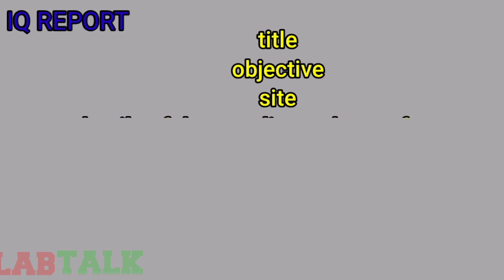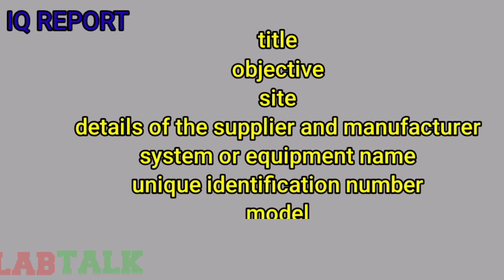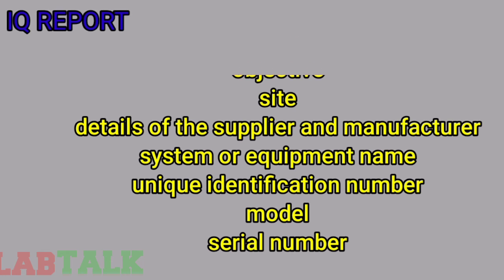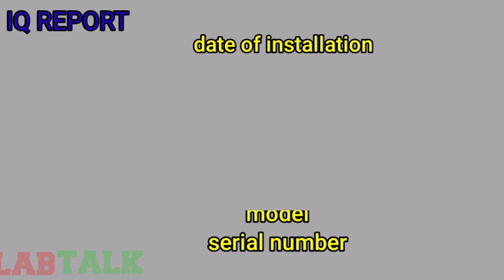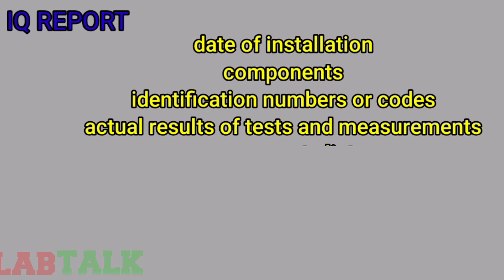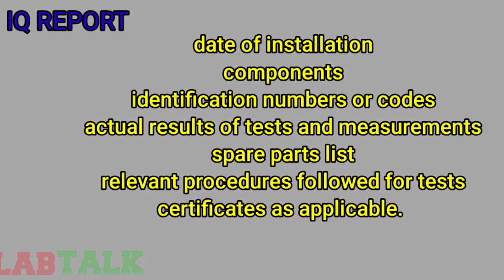Now, the next part is how to write the report. After doing an actual installation qualification, you need to mention everything in detail in the report, which is the proper documentation for installation qualification. The execution protocol should be recorded in the IQ report.